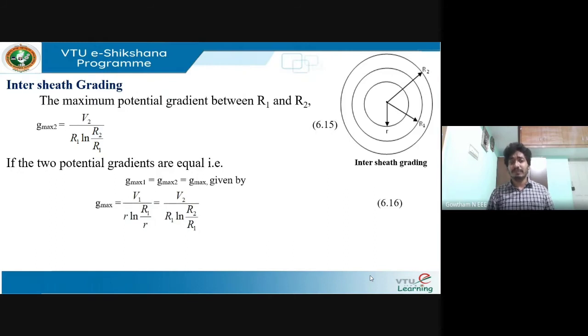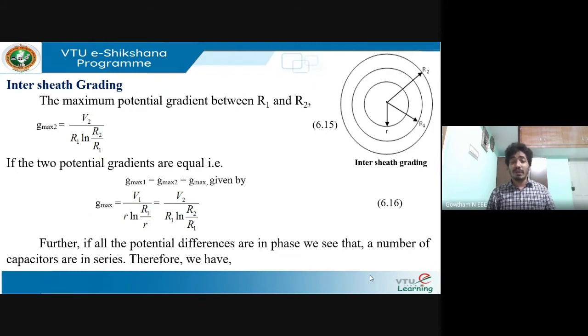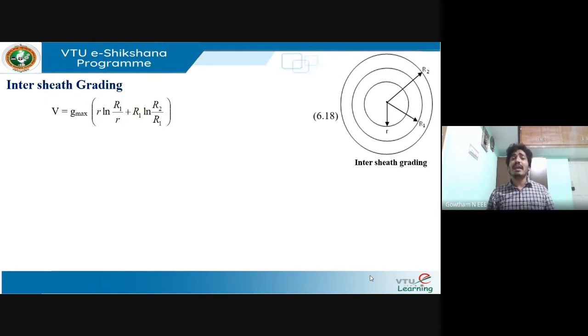When the two potential gradients are equal — g_max1 = g_max2 — we get: v1 / (r × ln(r1/r)) = v2 / (r1 × ln(r2/r1)). If all potential differences are in phase, the capacitors are in series, so V = v1 + v2. On equating, the total voltage is: V = g_max × [r × ln(r1/r) + r1 × ln(r2/r1)].